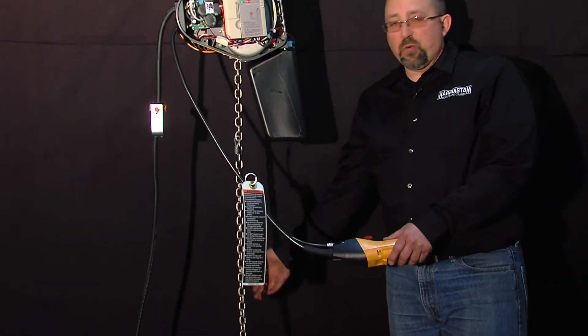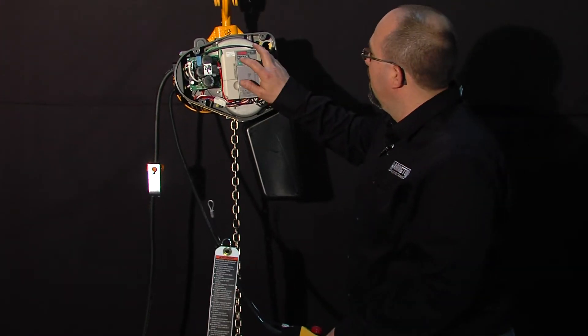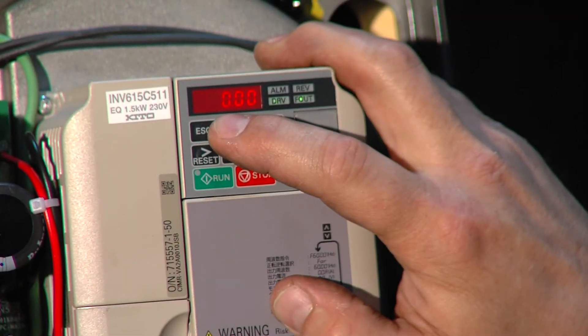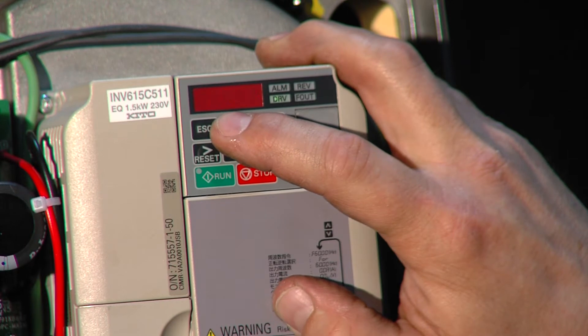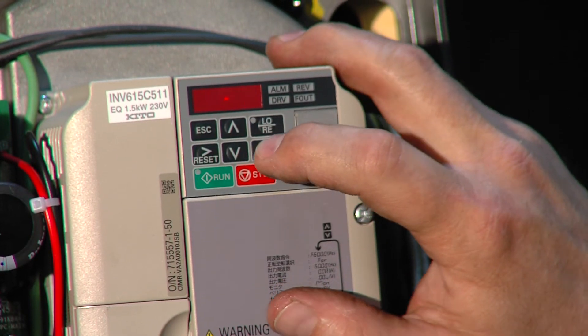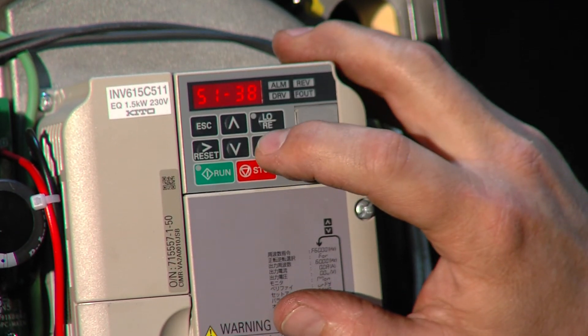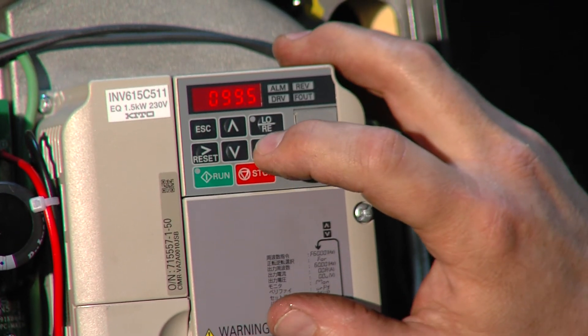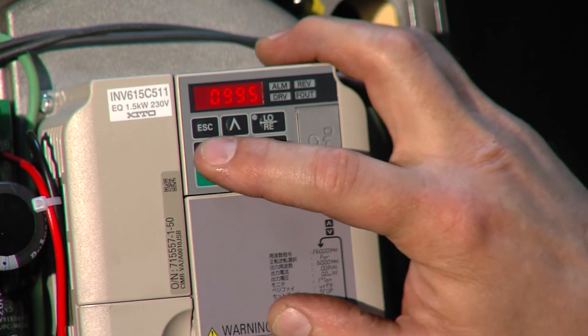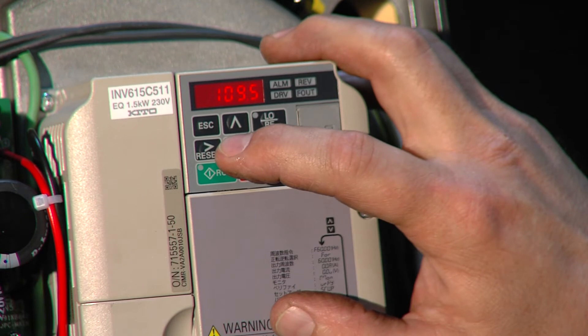So that we can lift this 2,758 pound test weight, we're going to scroll using the up arrow until we get to setup — STUP. Press the enter key, scroll until we get to S1-38. That's the first parameter we have to adjust. Press enter; right now it's set at 99.5. We're going to change that to 109.5.